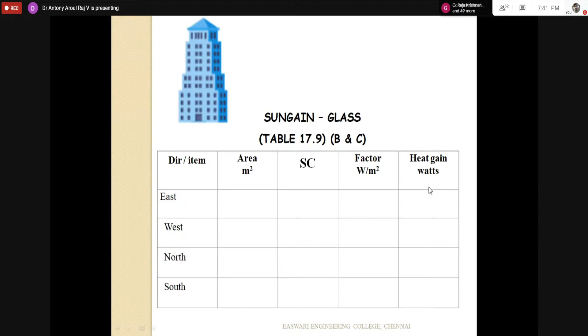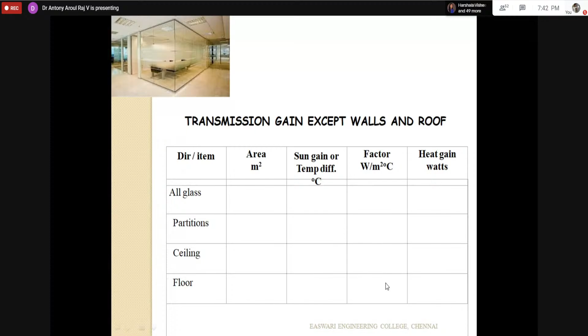Except exposed wall and roof, what are the other things? Next, room partitions, ceiling which is not exposed, and the floor. For all these, what is the area, what is the temperature difference, what is the U factor? Multiply and you get the sensible heat.